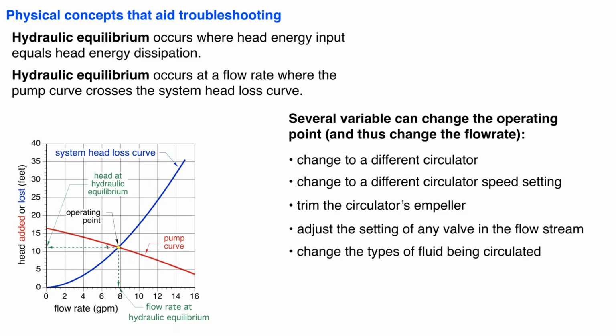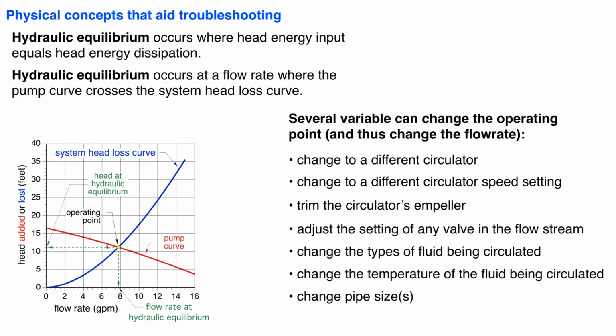All right. Changing the type of fluid. If we add antifreeze to water, we're going to change the viscosity and the density of that fluid. That is going to have a bearing on that system curve. Higher viscosity is basically going to steepen up the system curve and give us a lower flow rate. Even changing the temperature of the fluid, in theory, has some effect. Cooler fluids are more viscous than warmer fluids. And again, the viscosity does change that system curve.